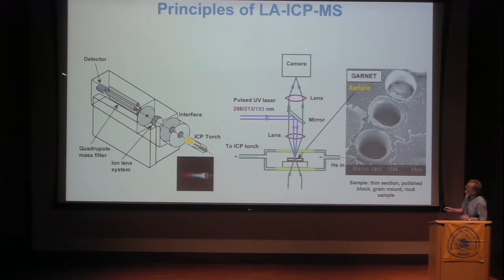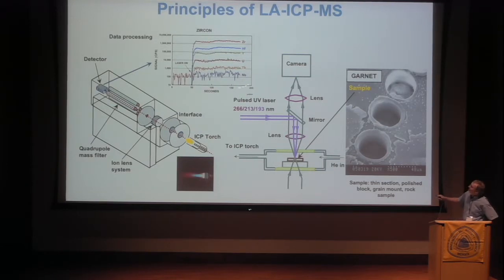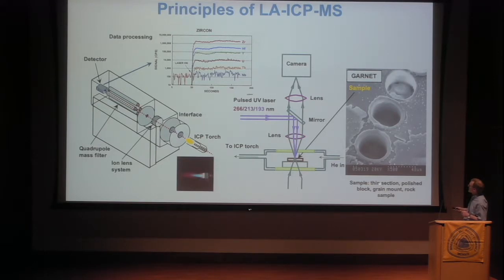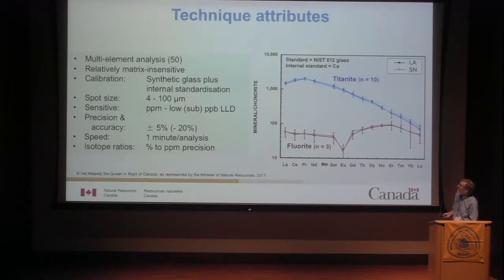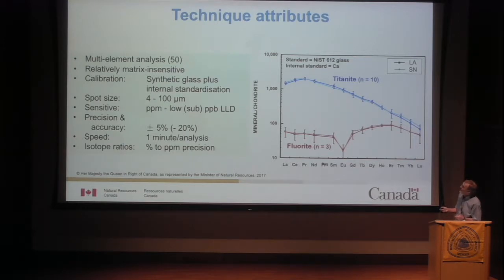Most ICP-MS is a single detector instrument, so you switch the voltages on the quads to let each ion of different mass through to the detector sequentially. Those counts are sent to a computer for data processing. The beauty of this technique is its flexibility — you can analyze almost any sort of sample with very little sample preparation: thin sections, polished blocks, grain mounts. As long as you can fit it into the cell, you can analyze it. You can analyze most elements in the periodic table, except for a few light elements. We typically analyze 50 elements or so simultaneously.